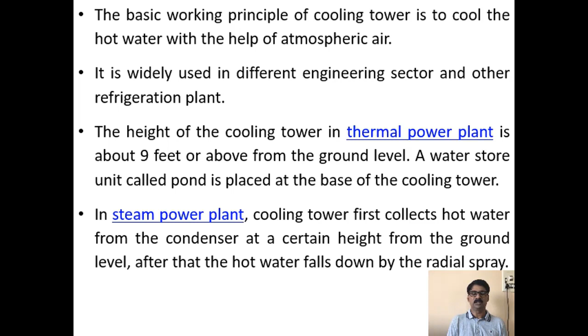Now in order to recirculate the same water, this hot water has to be cooled using a cooling tower, whereas the condensate water which is at low temperature is fed back to the boiler using a pump. So this is how a cooling tower is made use of in a steam power plant. Here the hot water which is collected from the condenser by the cooling tower will be sprayed at a height, and it falls down through this cooling tower.